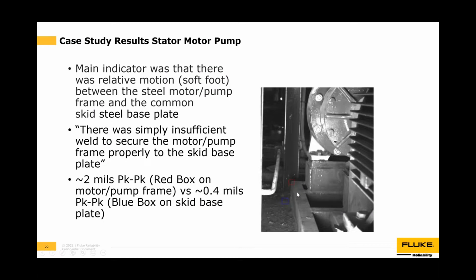So what they did here, you can see where they measured, there's a little red box and a blue box. They found a very big differential between those measurements, 2 mils to 0.4 mils. There's relative motion between the motor and pump frame and the skid plate, the base there. So it wasn't sufficient enough.